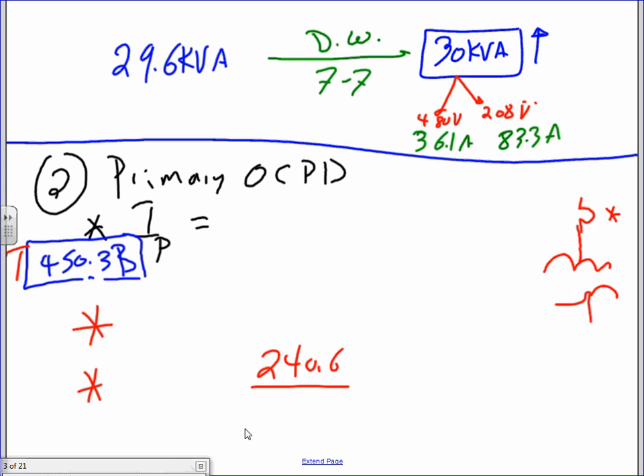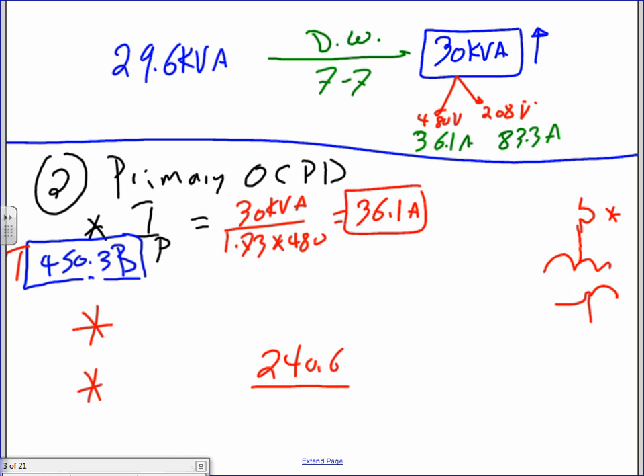Now the second thing we need to do, number two, is the primary overcurrent protection device. So Adam, we sized the transformer. We need to size the fuse or the circuit breaker ahead of the transformer. If you guys go to table 450.3(B), which we were in many times, since we're doing the primary, the first thing we need to find is the full load current of the 30 kVA. By the way, it's already here. Here's the number right here. 1.73 times 480 should come up with 36.1 amp, and it's already given there in the table. But that's how you do it if you do the calc.